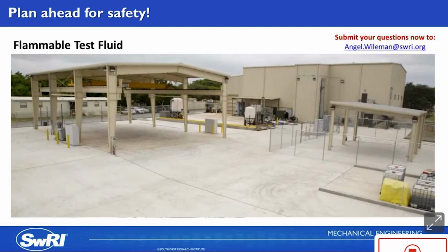Now, the fugitive emission setup is obviously not near as extensive as that one, but it should follow the same general practice of being performed in a well-ventilated space within a fenced-in area and isolated from all non-rated electrical equipment. The fenced-in area shown to the right here is where we perform our fugitive emissions testing with methane to API standards.